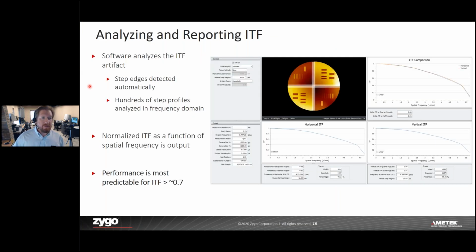And as we just saw, the step edges are detected automatically. Hundreds of step profiles are drawn. Normalized ITF as a function of spatial frequency is output. And we should note here that performance is most predictable.